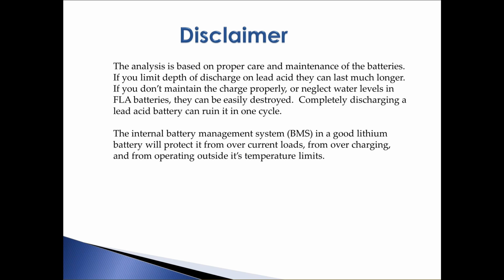The internal battery management system in a good lithium battery will protect it from overloads. It'll shut off the output if you try to pull too heavy a load, it'll shut off if you try to overcharge it or if your charging voltage is too high, and it'll also keep you from operating outside the temperature limits. So it's a relatively safe system in terms of protecting itself, given that it's an expensive investment.